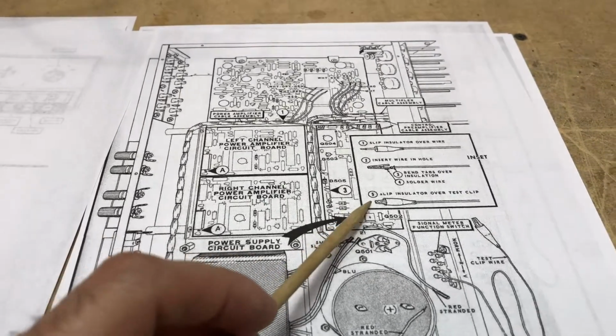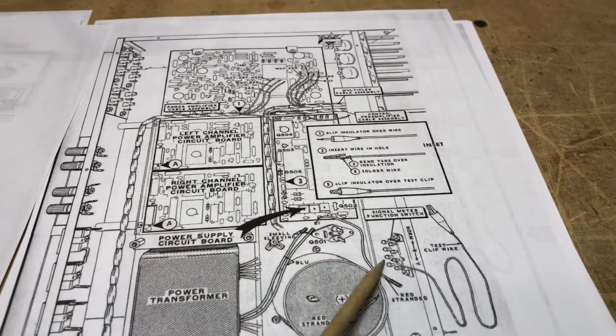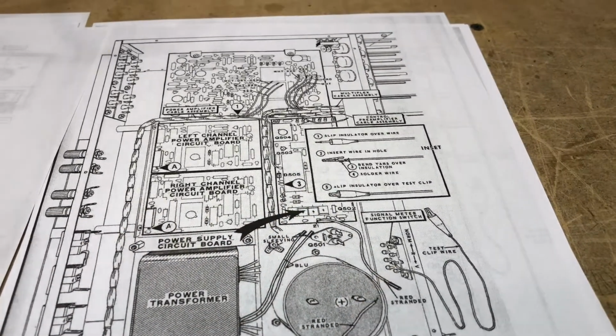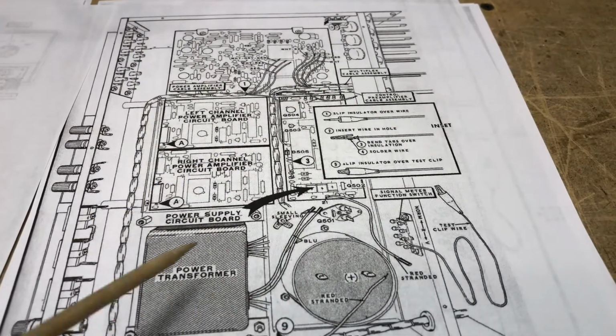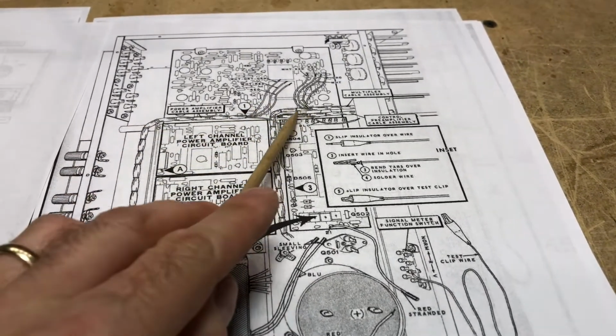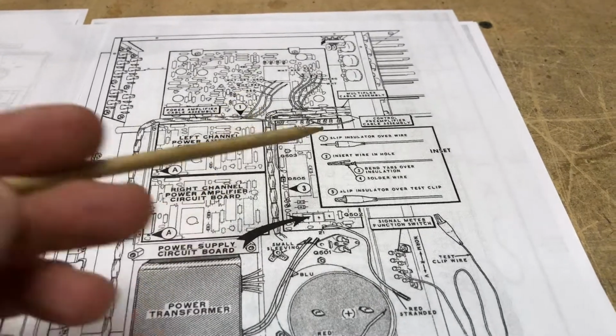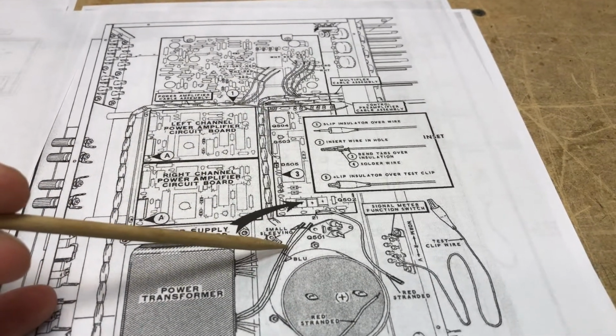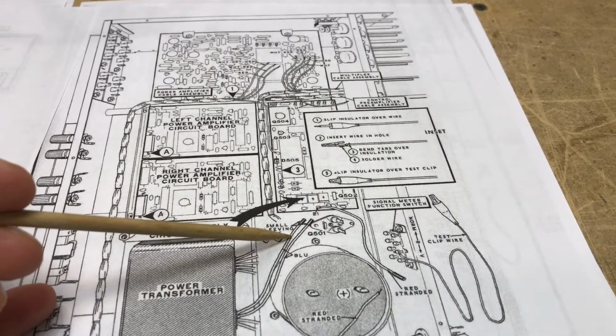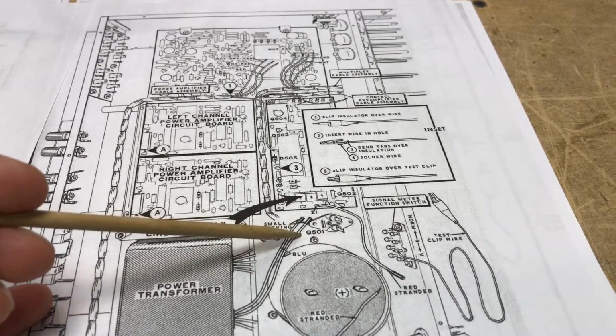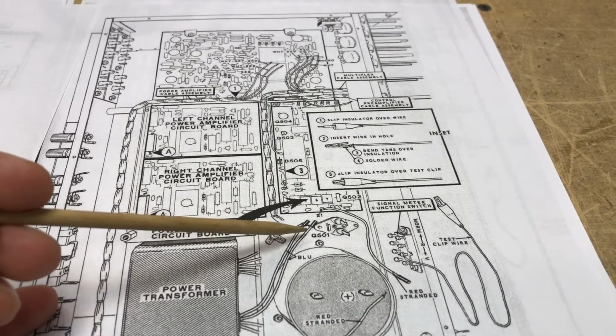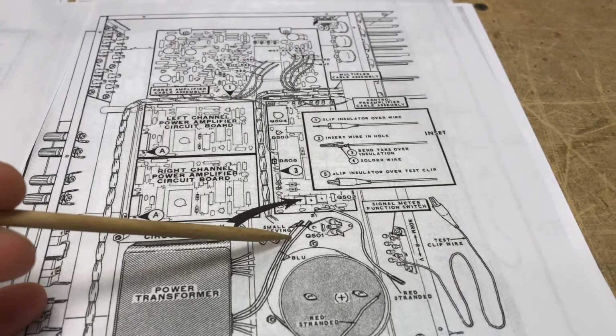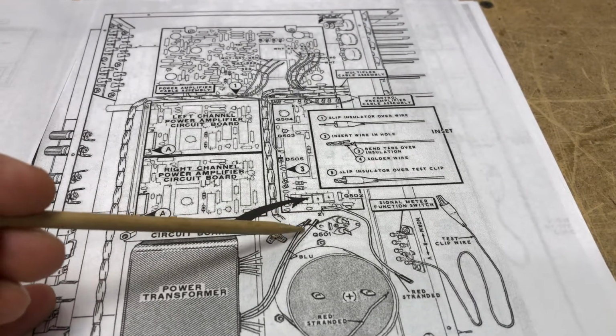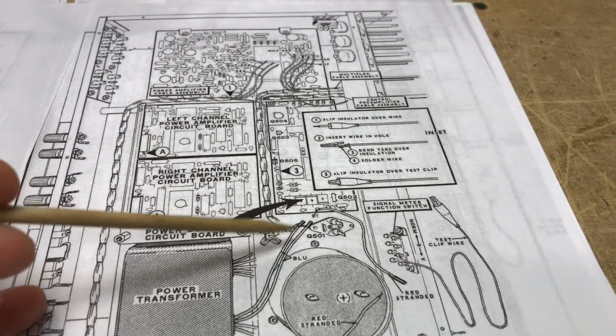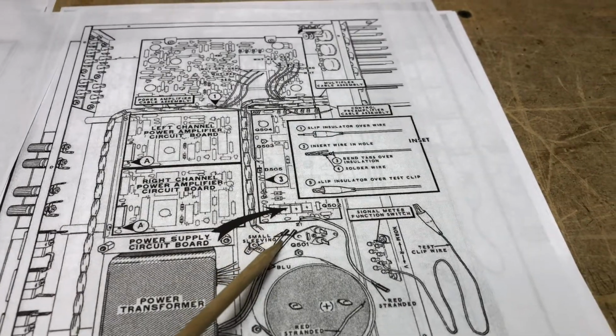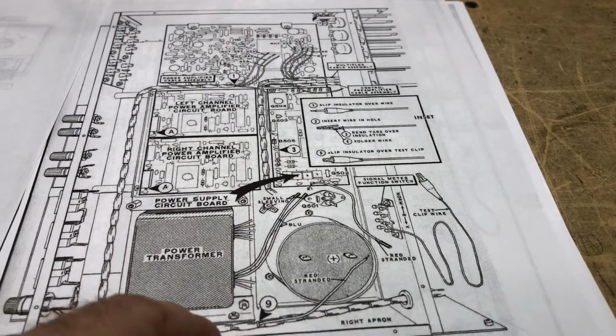Here's where it tells you how to hook up the little test clip to the meter selection switch, and here's where it spells out the leads that will still remain disconnected. Two of the leads, these blue leads, carry 100 volts AC coming out of these transformer leads. So if you do this, make sure you take the appropriate precautions — you don't want to electrocute yourself, since that's high voltage coming out of the transformer.